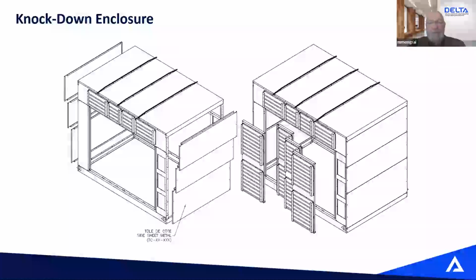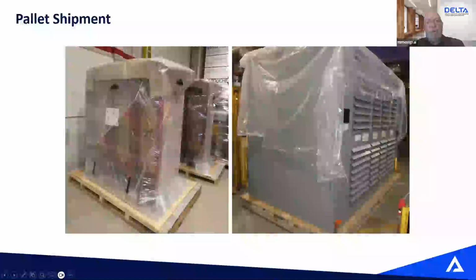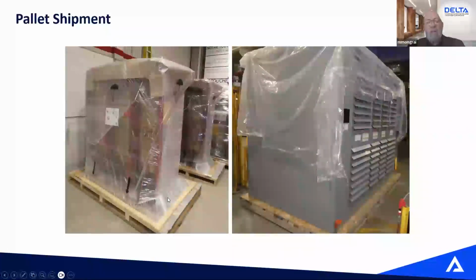So depending on the access, you may have to disassemble the enclosure in part or totally to bring it into the room. Usually we ship the transformer fully assembled on a skid like this. At Delta, this is unique in the industry. All of our power transformers are shipped on a wood skid. There's good reason for such. First reason, between our core and coil and our enclosure, there's no mechanical link. The feet of the core and coil are not attached to the enclosure. So this is to prevent, I would say, vibration transmission from the core and coil to the enclosure.